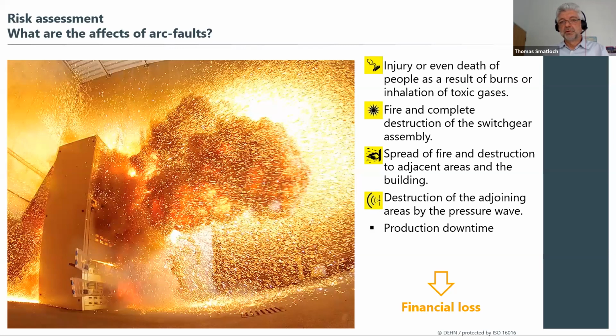It can lead to a complete destruction of the switchgear assembly, of course, and the fire can spread to other parts of the installation as well, and can burn a lot. It can lead to destruction of the adjoining areas by the pressure wave as well, because such a gas also develops a high pressure in this field. And not to mention, of course, the downtime in production where this application is located, and the financial loss which results from such an event.